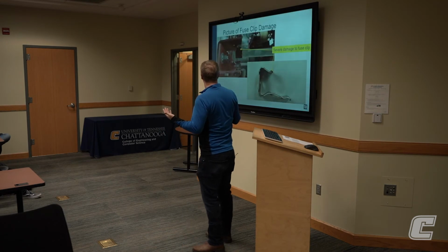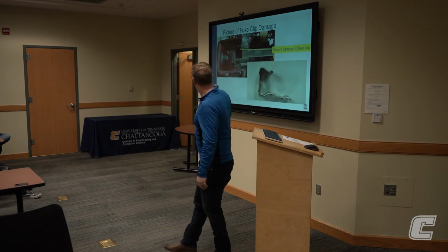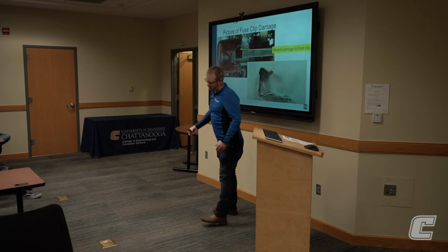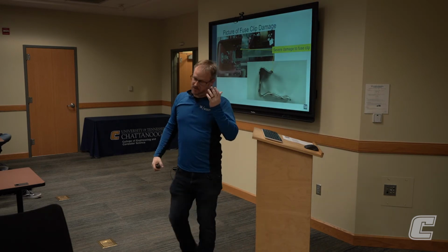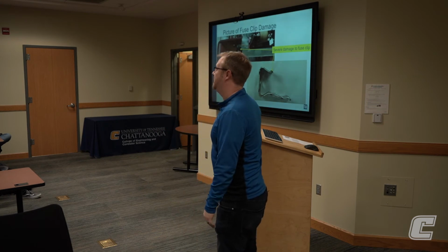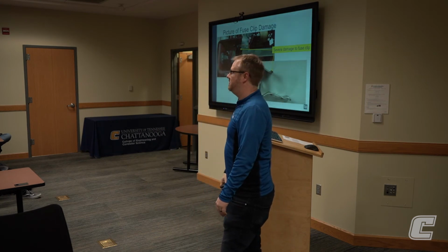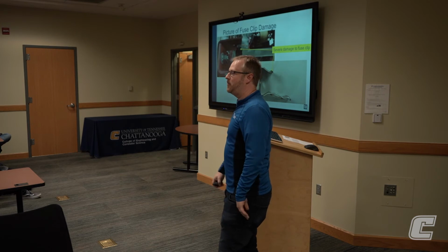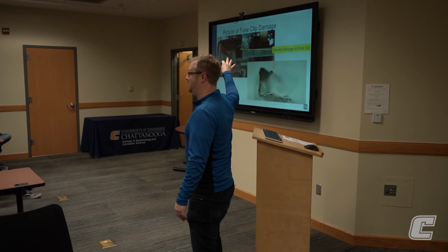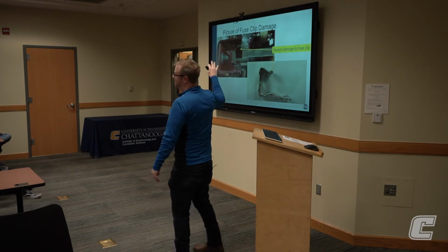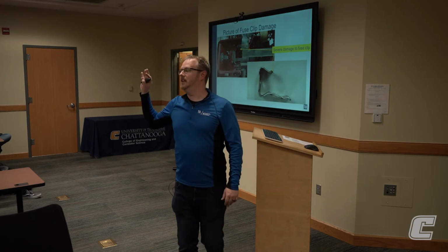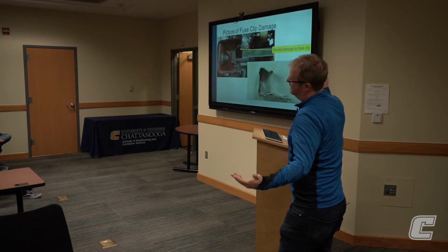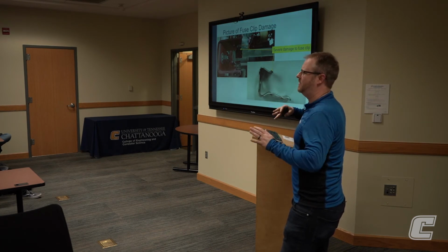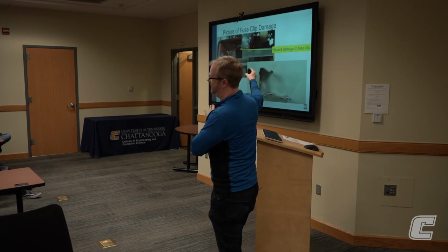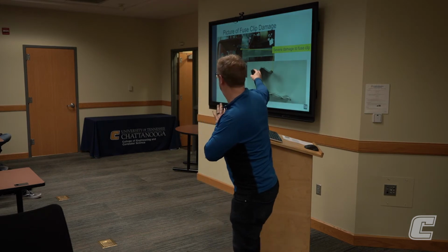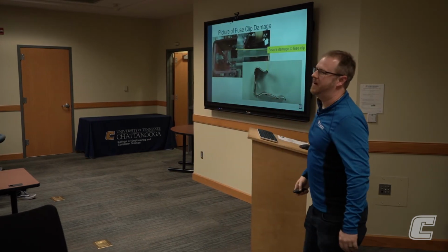And this was a great catch because had this failed, where this fuse would have fallen out and it would have tripped the unit, it would have cost TVA quite a bit of money, potentially damaged some equipment. So we got lucky. We thought it was a unit oscillation, which we'll see in a minute. That's not what happened here, but the synchrophasor data and the tool caught this, which was good. And now we know how to look for it. Remember I talked about equipment failure detection? This is a perfect example. We weren't really focused on equipment failure detection here, but that's what we ended up finding.